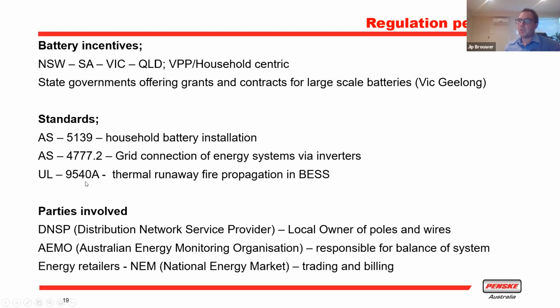And the last one is the UL 9540A, which is a battery standard on the cell or module level, which tests what happens if you have a runaway cell. They purposely make a cell catch fire and see what happens to the other cells directly around it. And Samsung, as I said before, those cells don't ignite each other if there's a fire within one of the cells.